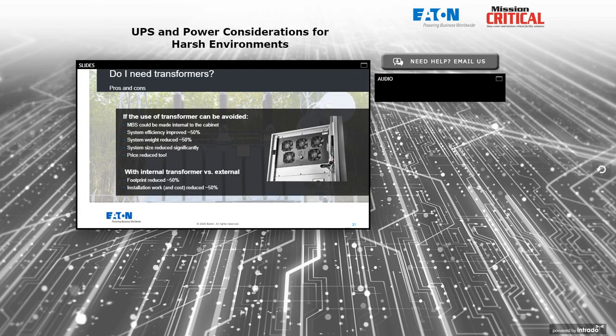So the value of these features, let's review real quickly. Do I need transformers? If I can avoid transformers, the maintenance bypass might have enough room to be mounted inside the cabinet, but in most of our applications, we like to see the maintenance bypass or the wraparound bypass external from the electronics cabinet because it's safer to service. If I'm able to avoid the use of transformers, my system efficiency can be improved significantly, as can the size and weight, as you can imagine, by removing the transformers. And that would impact the price as well.